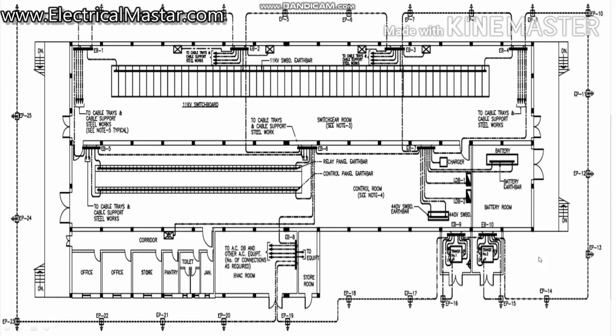See this earthing layout. Actually, this is outside the boundary of this drawing. This is called the substation. So these are the walls of the substation, and these are the entrance doors of the substation. And see here inside, this is the 11 kV switchgear board. The 11 kV switchgear board is connected this side, and this is the RCP panel, the remote control panel for this 11 kV switchgear. And on this side you can see the 440 volt switch board, the battery charger and lighting DB here, and this is the battery room to support this battery charger and control supply for the switchgear.